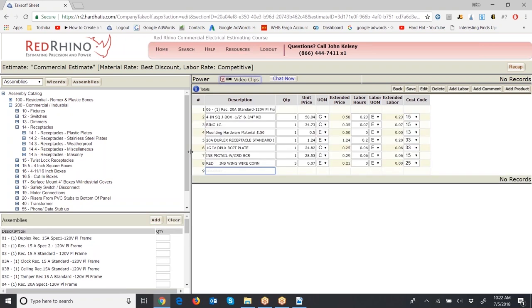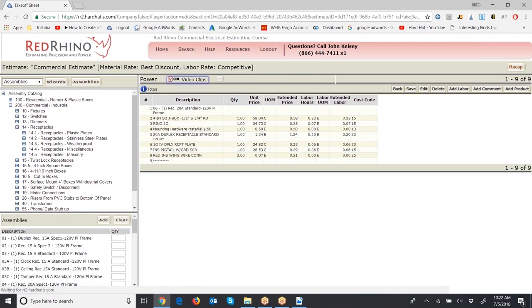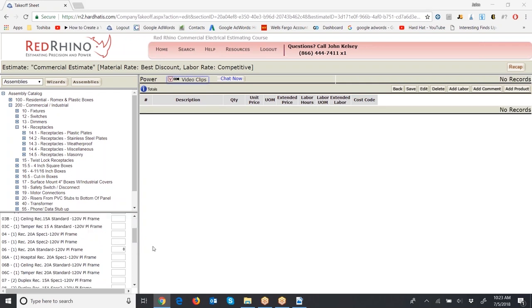The assembly for a duplex receptacle includes a 4S box, a plaster ring, mounting hardware (50 cents), the duplex receptacle, the plate, a ground pigtail, and wire nuts. That's what one assembly consists of. I'm going to delete these and input eight of these assemblies as shown on the takeoff sheet — quantity of eight, assembly number six, which reads: receptacle, 20-amp standard, 120-volt, PL (plastic plate), frame (open wall). Scroll up and click the 'Add' button.